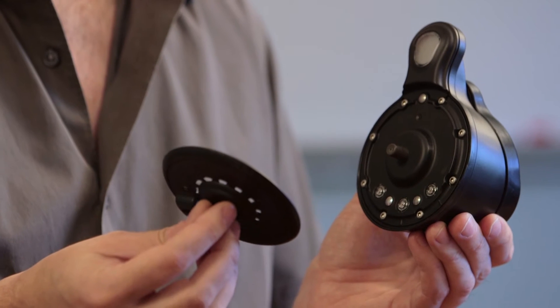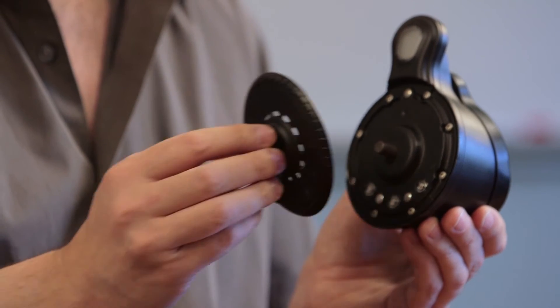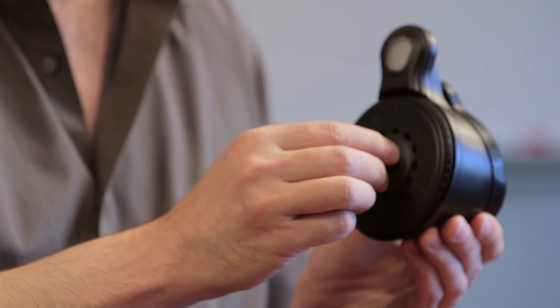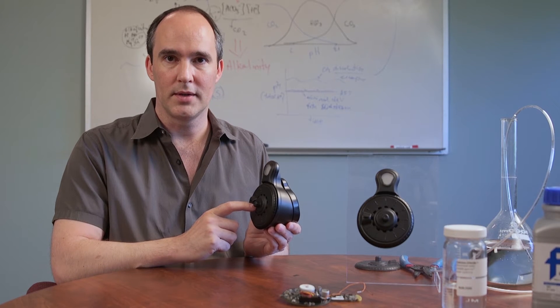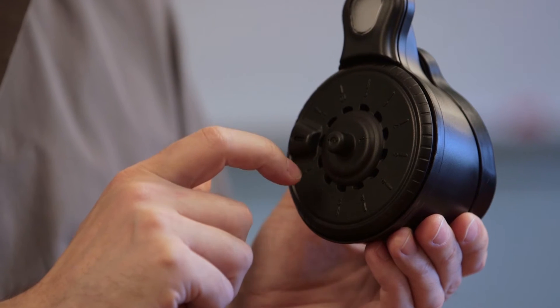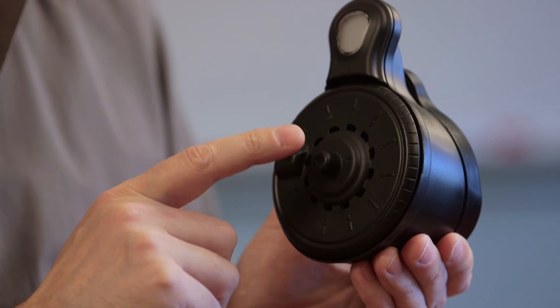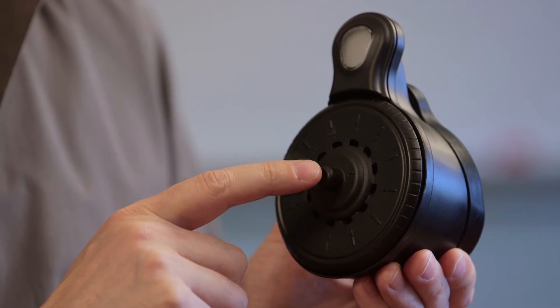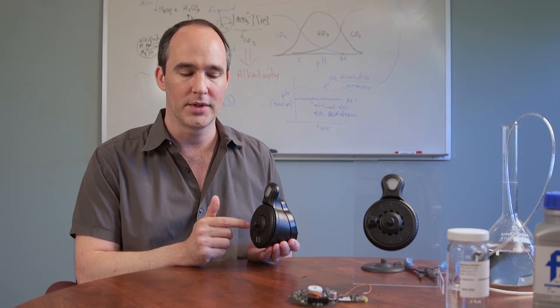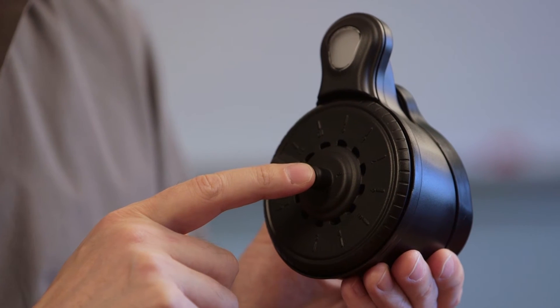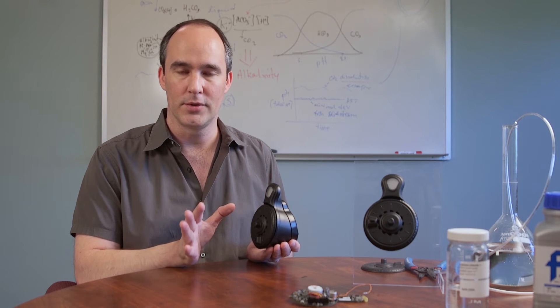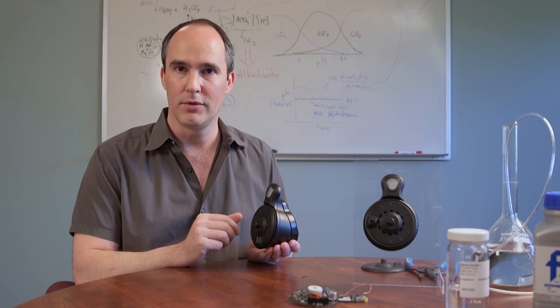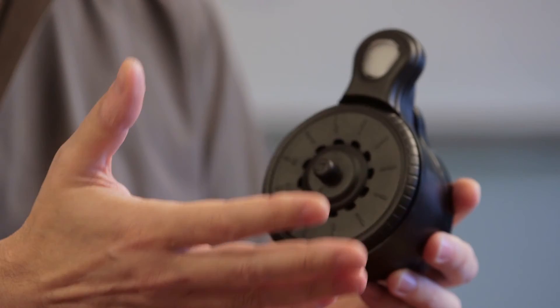Once that's set, all you have to do is take the sensor disk and install it on the hub of the Mindstream system. An RFID tag within the disk identifies itself to the monitor. The monitor downloads the calibration data for your disk and the identification for your disk so that the cloud servers know which disk you are using. There's no calibration necessary for the user, and you don't need to be a chemist to use this device. It's that easy.